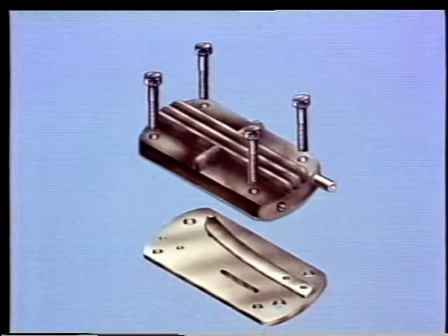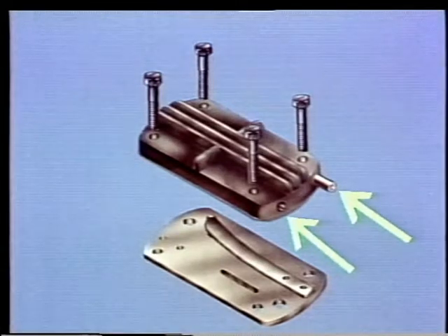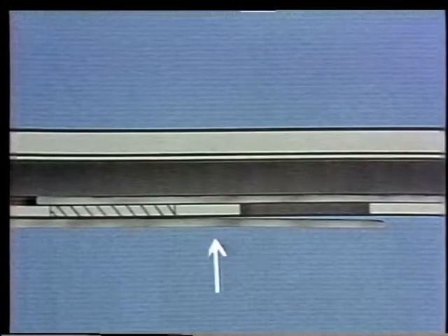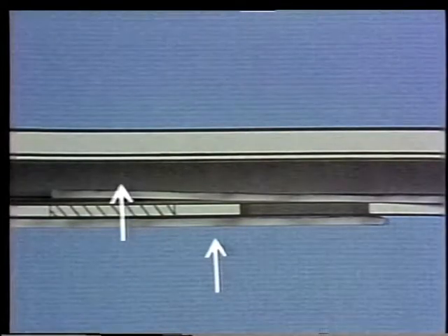Above the seat and the feathers is a guard plate that contains an inlet port and a discharge pipe. On a downstroke, the pressure differential across the valve causes external air pressure to push open the lower feather, allowing air into the cylinder while holding the upper feather shut. On an upstroke, the pressure in the cylinder shuts the lower feather and pushes the upper feather open.